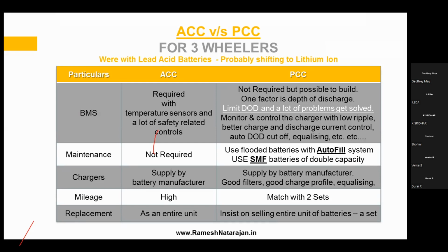Because this has already been experienced with all the stationary batteries used in solar applications, where the depth of discharge is very, very low. The batteries last for 10, 12, and even more years. I'm not saying we have to limit it to 20% depth of discharge, but if we bring it somewhere close to 60 or 70% depth of discharge, then the variations in the various cell gravities will not be there, and it will be possible to not have the problems which we are facing now.